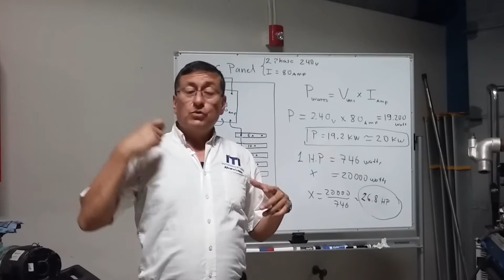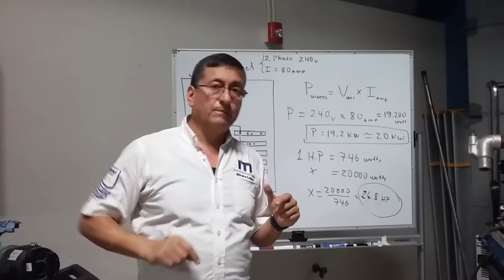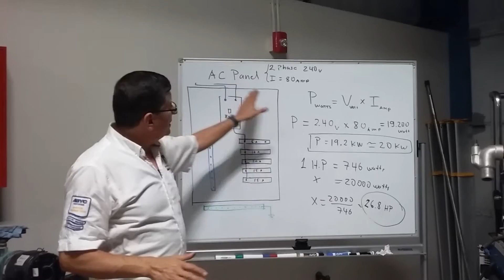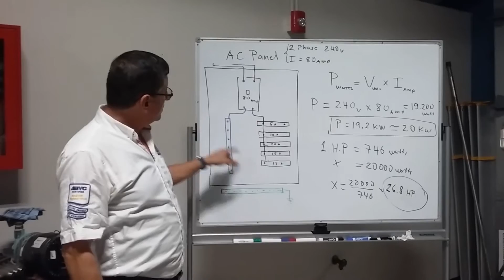Normally, when a customer calls me regarding a new generator, my first step is to visit the boat and check the AC panel. And with the AC panel, I can calculate the power required to supply all the equipment with my new generator. This is the procedure. Suppose that this is the actual AC panel. The AC panel normally has the main breakers, the neutral bus bar, and the ground bus bar.